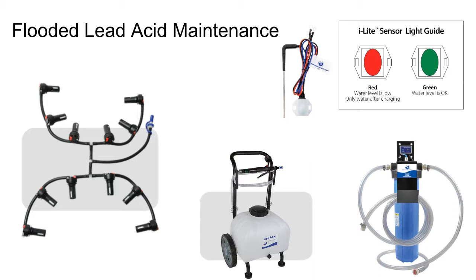Battery maintenance, it's not so hard. Each of the batteries, you have to put water in them. And the water needs to be distilled water. It can't just be tap water. For that matter, your battery rooms should be air conditioned. A lot of air conditioners, kind of the portable units, can suck water vapor out of the air and create their own water. So there you go.